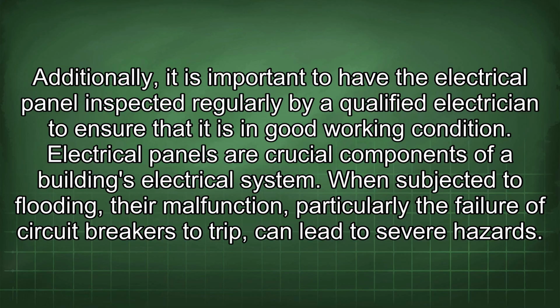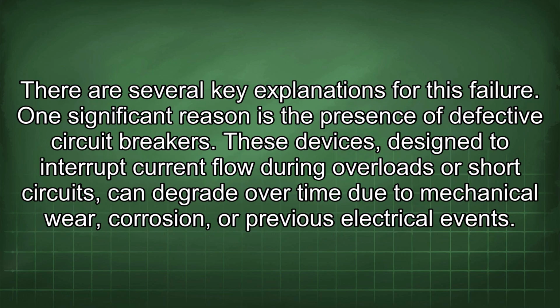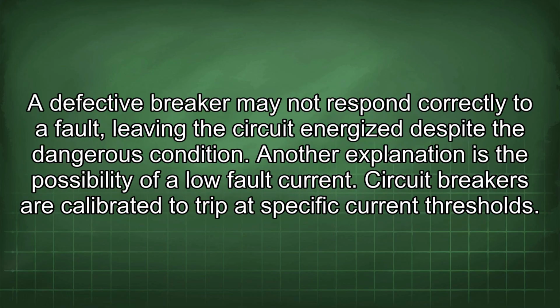Electrical panels are crucial components of a building's electrical system. When subjected to flooding, their malfunction, particularly the failure of circuit breakers to trip, can lead to severe hazards. There are several key explanations for this failure. One significant reason is the presence of defective circuit breakers. These devices, designed to interrupt current flow during overloads or short circuits, can degrade over time due to mechanical wear, corrosion, or previous electrical events. A defective breaker may not respond correctly to a fault, leaving the circuit energized despite the dangerous condition.